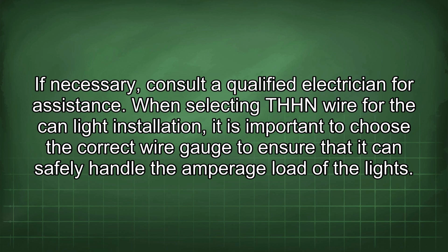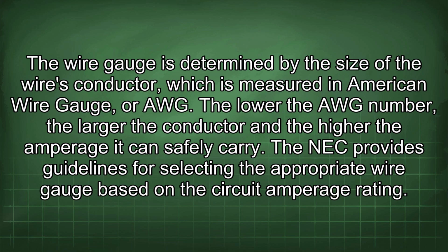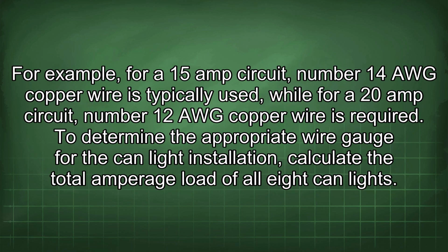When selecting THHN wire for the can light installation, it is important to choose the correct wire gauge to ensure that it can safely handle the amperage load of the lights. The wire gauge is determined by the size of the wire's conductor, which is measured in American wire gauge, or AWG. The lower the AWG number, the larger the conductor and the higher the amperage it can safely carry. The NEC provides guidelines for selecting the appropriate wire gauge based on the circuit amperage rating. For example, for a 15 amp circuit, number 14 AWG copper wire is typically used, while for a 20 amp circuit, number 12 AWG copper wire is required.